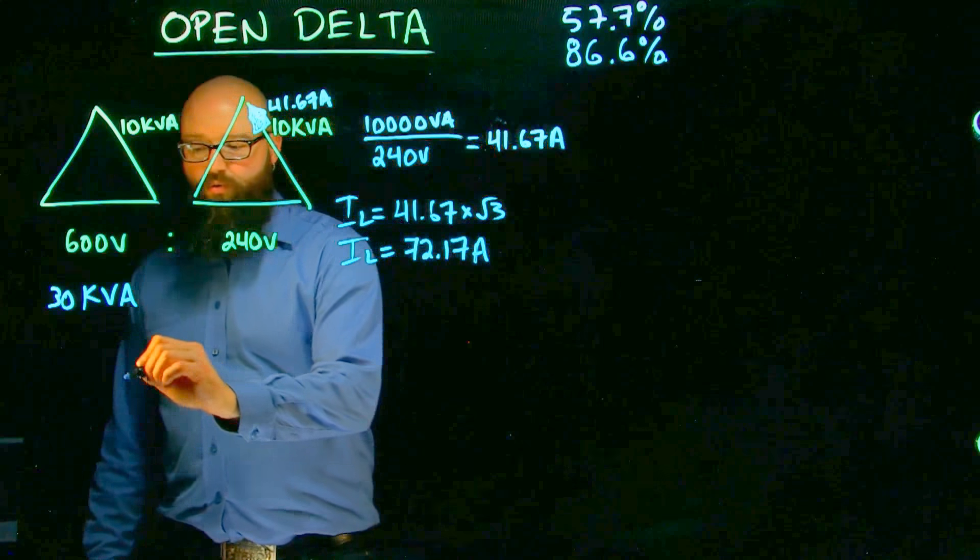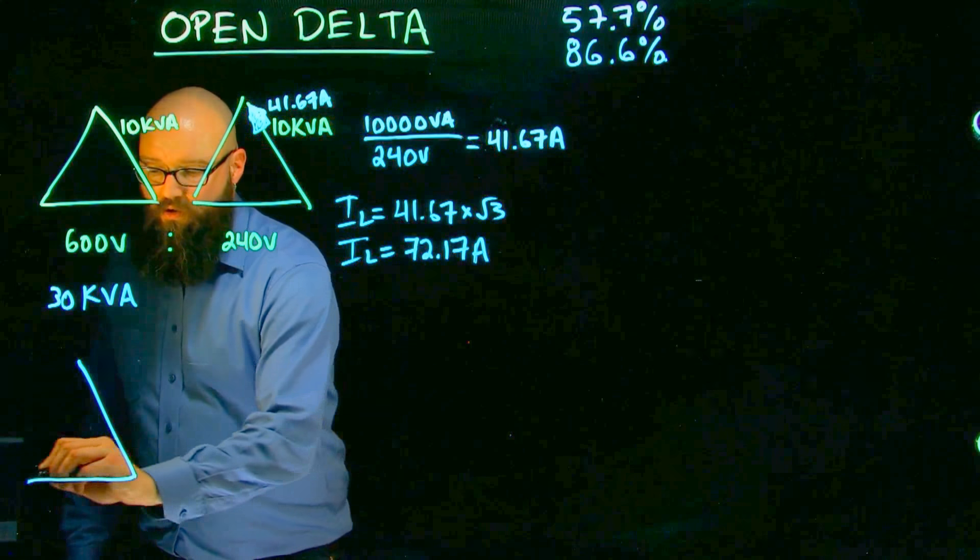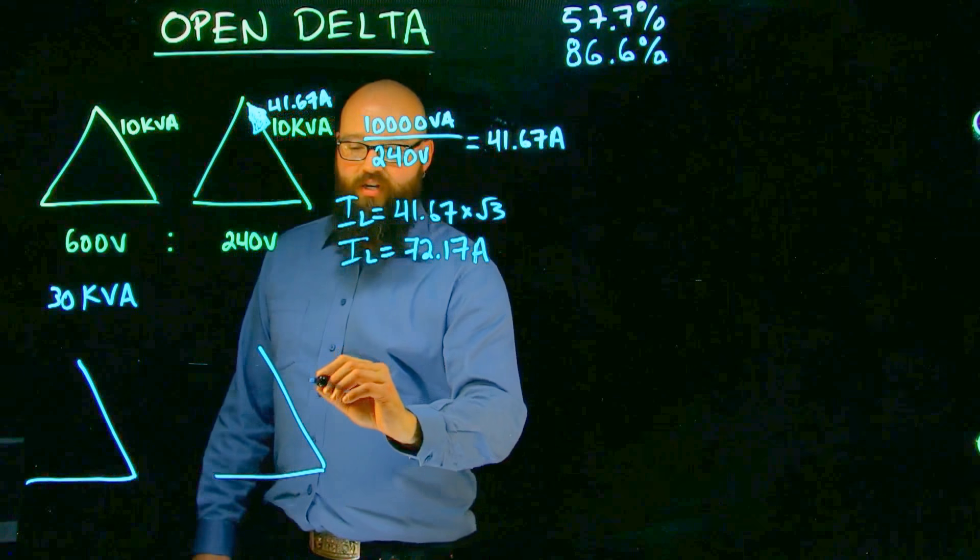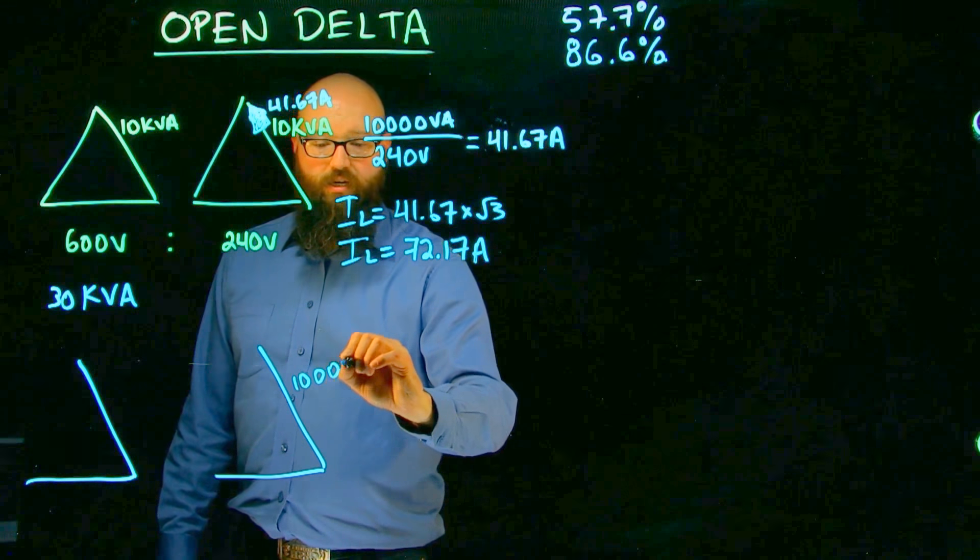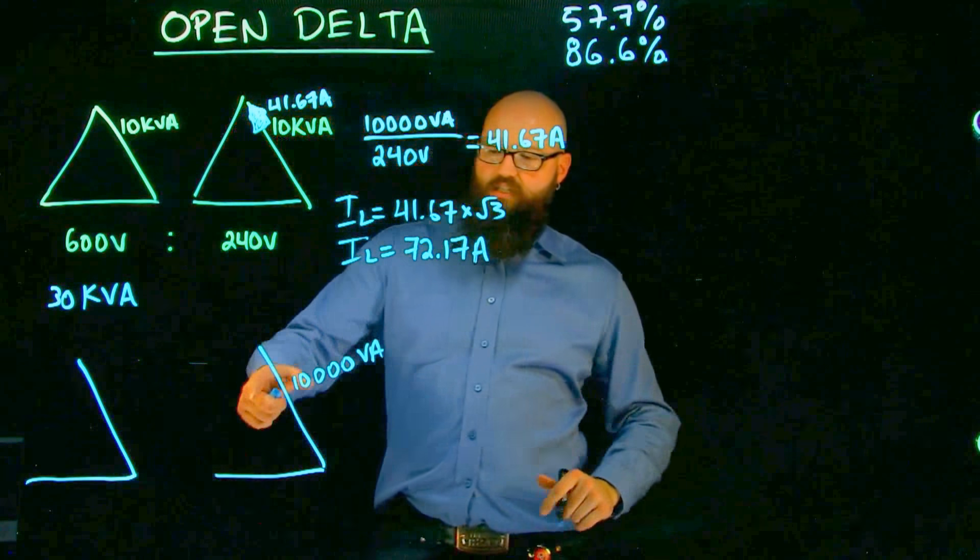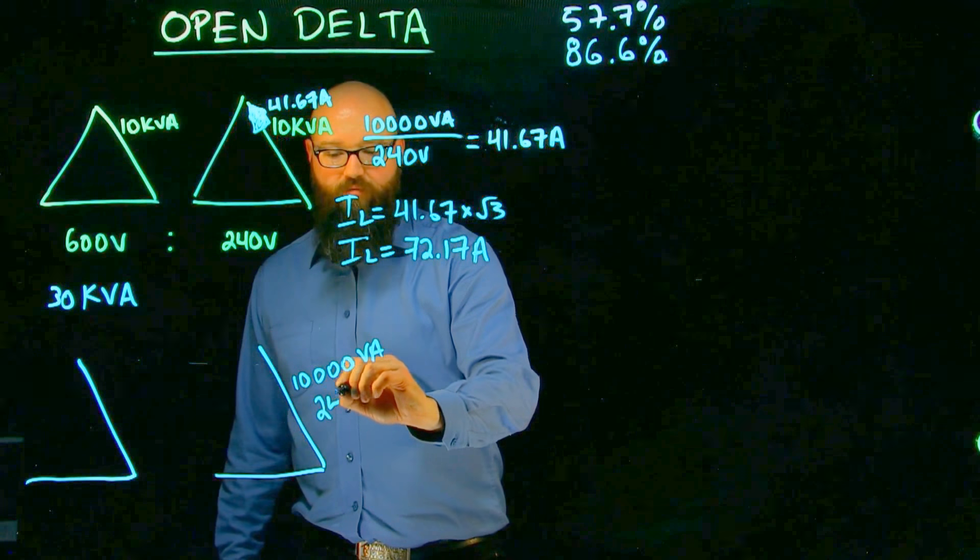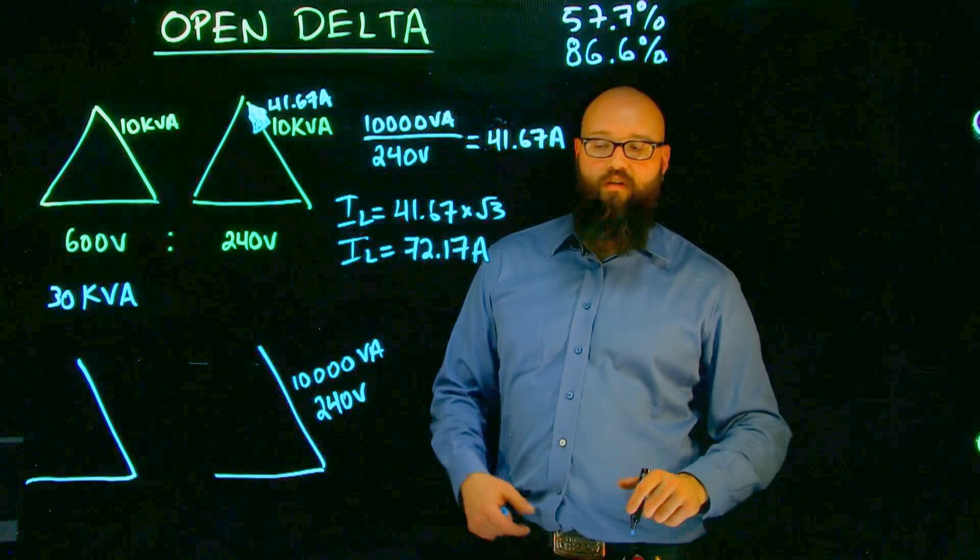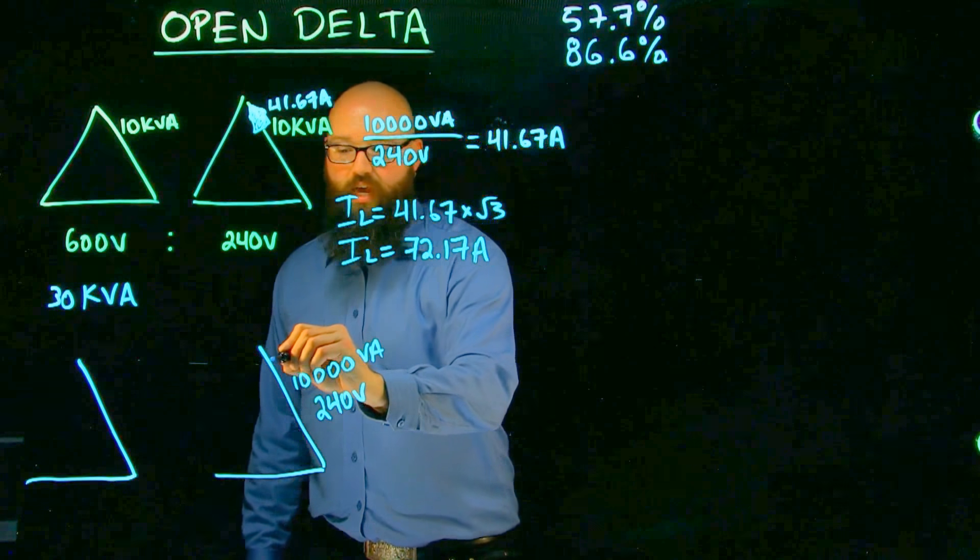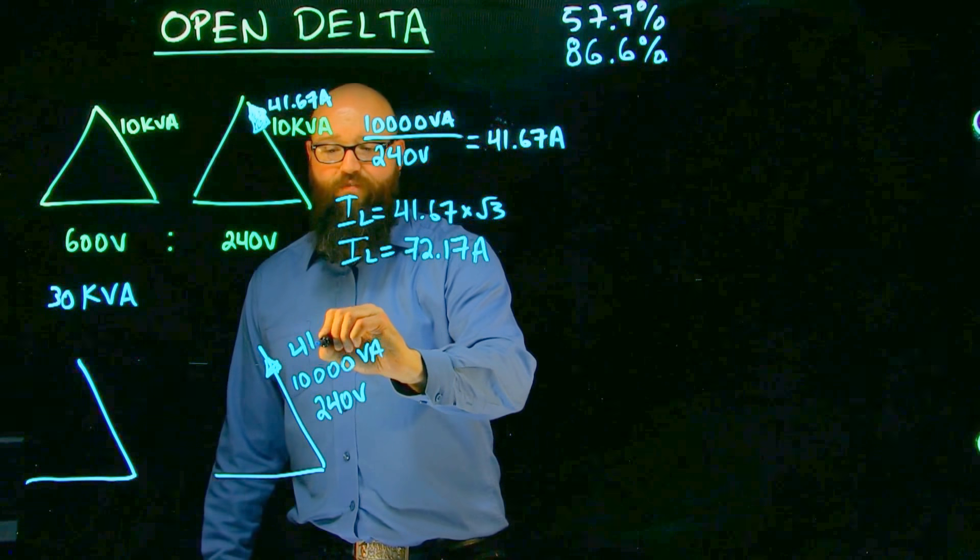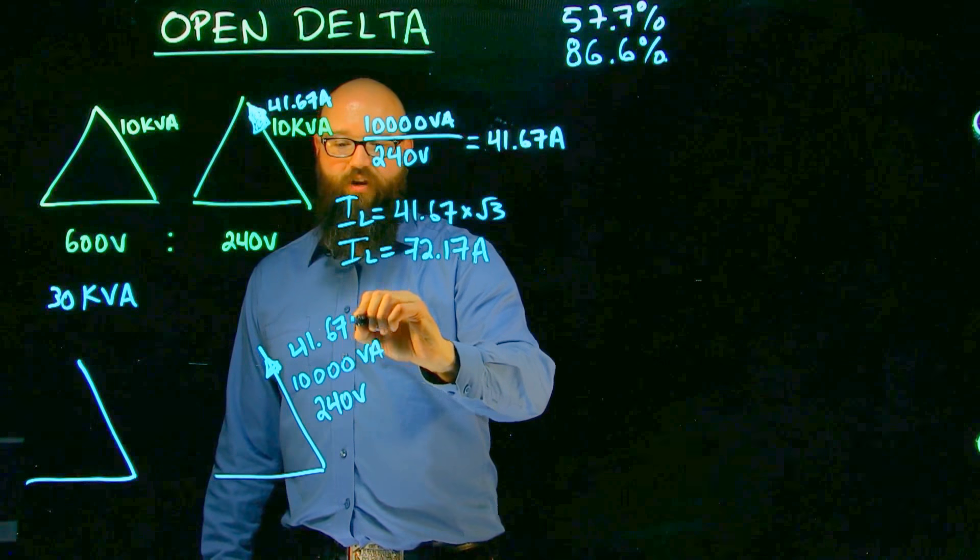However, what happens when we lose one of those windings? Okay, each one of these windings is still rated at 10,000 VA. Okay, and it has still 240 volts induced into the secondary side of it, which still gives us a phase current, if we do the same calculation, of 41.67 amps.